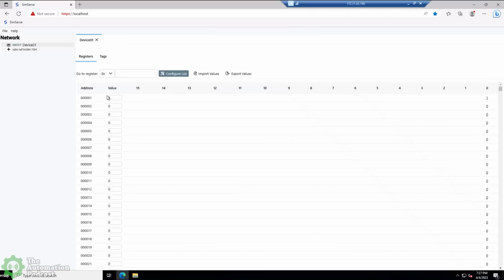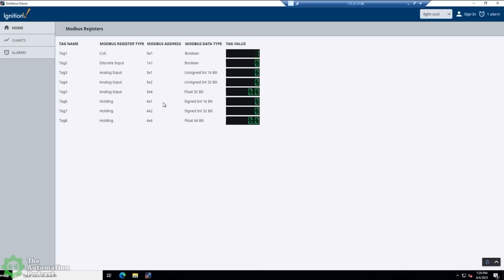And with that said, what I'm actually going to do now is flip over to my Ignition SCADA virtual machine here. Okay, so what I've just pulled up is an Ignition perspective HMI that I've pre-created just to be efficient with everyone's time here. And on this HMI screen, what you're seeing here is a list of 8 tags and their corresponding values. And these tags are just linked to Modbus registers in that SimServe device we already created. And so tag 1 right here is linked to Modbus address 0x1, and you see tag value of 1. That's because we activated that coil back when we were in SimServe. And so that's a pretty basic example.